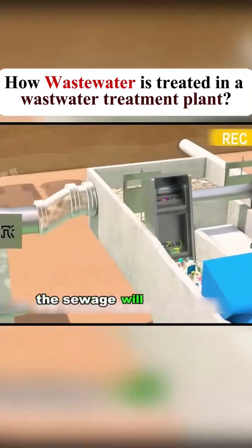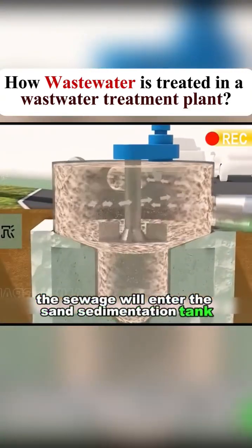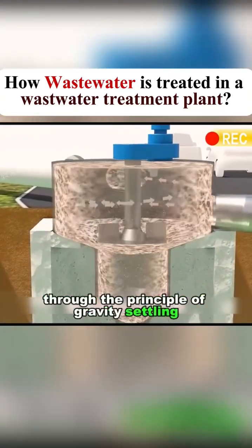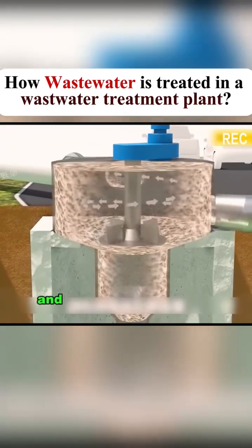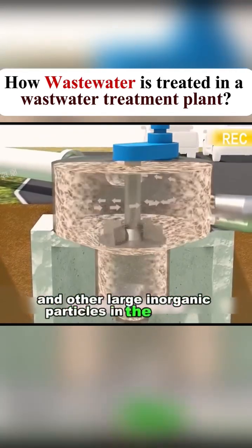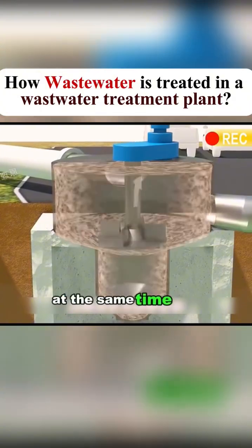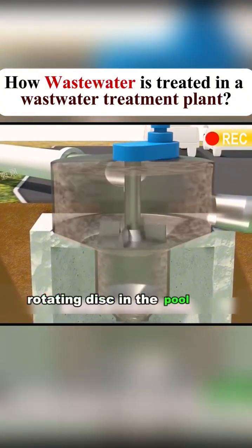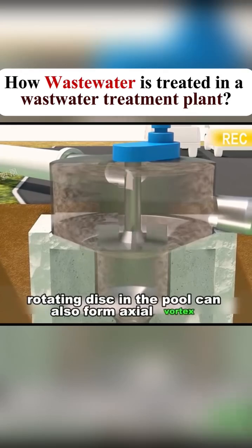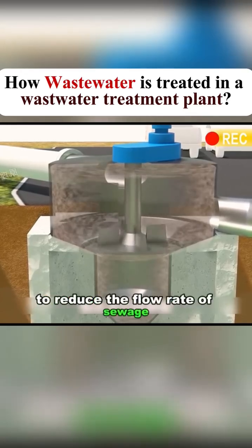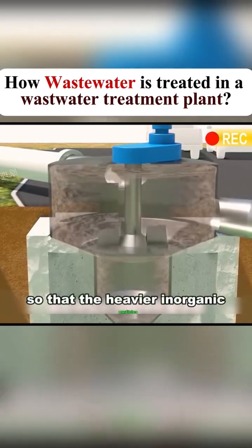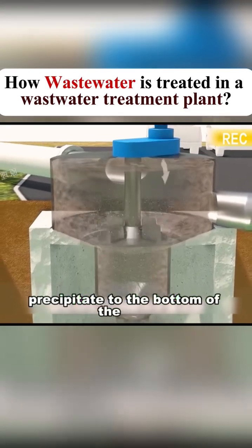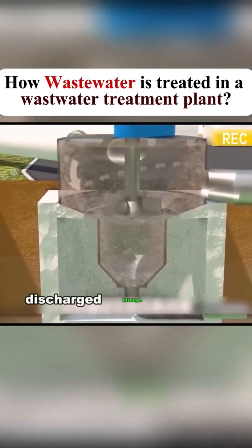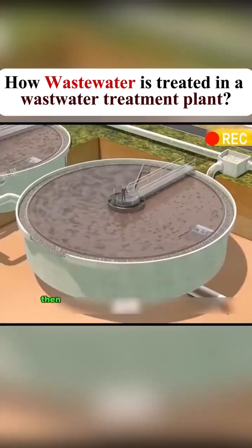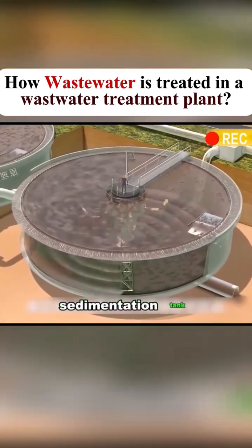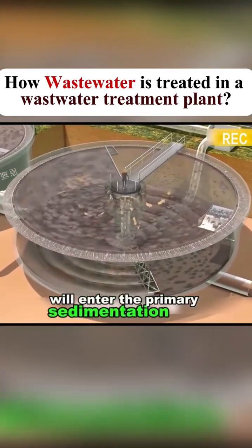Then the sewage will enter the sand sedimentation tank, where, through the principle of gravity, settling removes sand, cinder, and other large inorganic particles in the sewage. At the same time, the impeller rotating disc in the pool can also form an axial vortex to reduce the flow rate of sewage, so that the heavier inorganic particles precipitate to the bottom of the pool and are finally discharged through the sand discharge equipment.